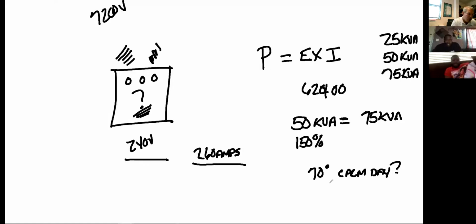Okay, all right, I'm at 150% and it's 112 degrees, hot and sunny. Should I put a 75 there? Yeah, I probably would, because it's starting to get up in the peak areas right there. So I'd probably go with, yeah, I probably need to go up to a 75 kVA just because of the conditions.